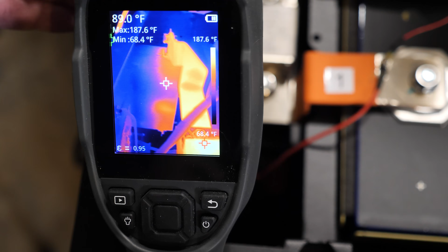This is the side of the DC circuit breaker. It's showing just 82 degrees. A little warmer spot down there around 100. So the circuit breaker, I would say, is doing really, really good. The hottest points in here right now, of course, are going to be the fuse, 185 degrees Fahrenheit.